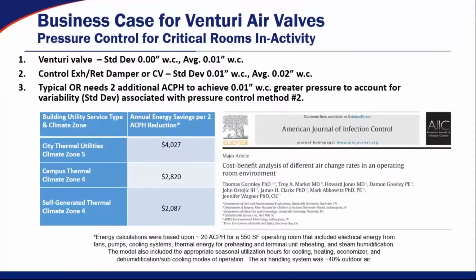Now, when you're talking about other critical environments, this is actually looking at an operating room inside of a hospital. This study was done between how a VAV box works and a Venturi valve or a Phoenix valve inside the operating room. Basically, what was trended was the differential pressure inside of that space. So looking at the pressure across the door. And in normal operating mode, the Phoenix Venturi valves had a standard deviation from 0 to 0.01 inches water column across the door. Now, if we contrast that to what you see with a VAV box or a damper set at constant volume, the standard deviation was twice that. It was from 0.01 to 0.02 inches water column, which is actually a pretty large deviation.